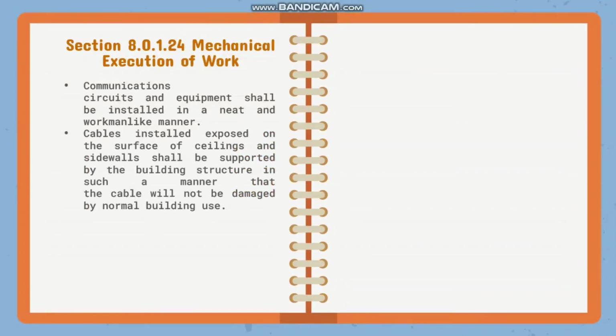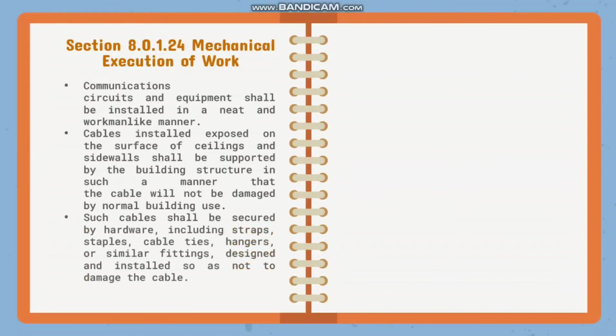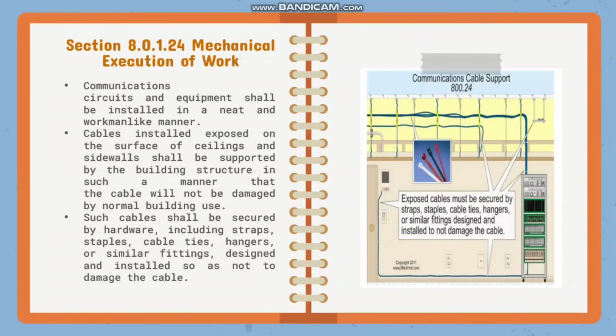Cables installed exposed on the surface of ceilings and sidewalls shall be supported by the building structure in such a manner that the cable will not be damaged by normal building use, and such cables shall be secured by hardware including straps, staples, cable ties, hangers, or similar fittings designed and installed so as not to damage the cable. So makikita po natin sa illustration na ito na na-meet niya yung mga requirements ng Section 8.0.1.24. So yung mga communication cable po ay naka-install in a neat and workmanlike manner sa surface ng ceilings and sa sidewalls, at naka-secure po sila gamit ang straps, staples, cable ties, and hangers.